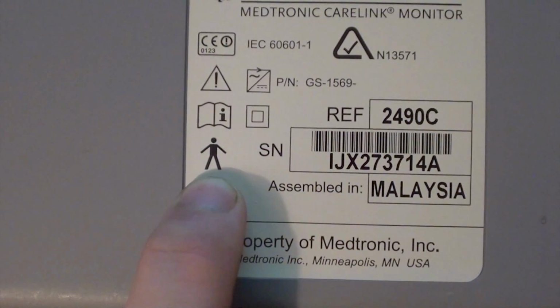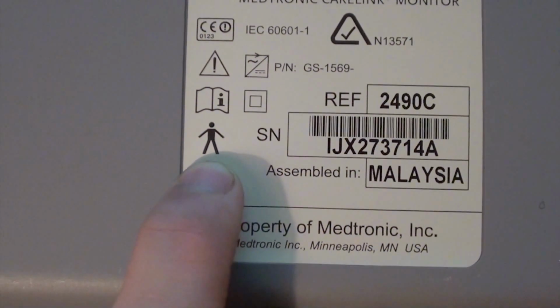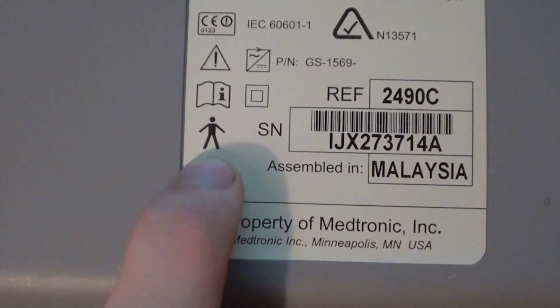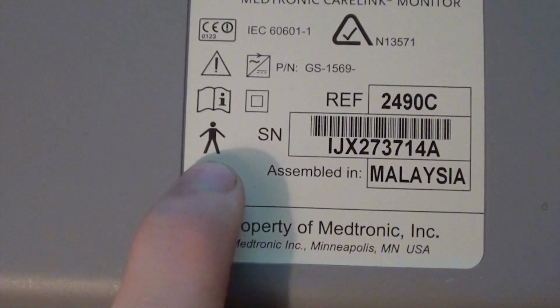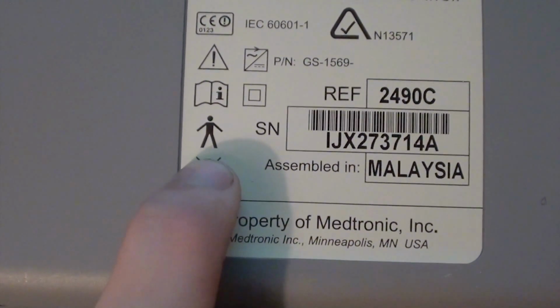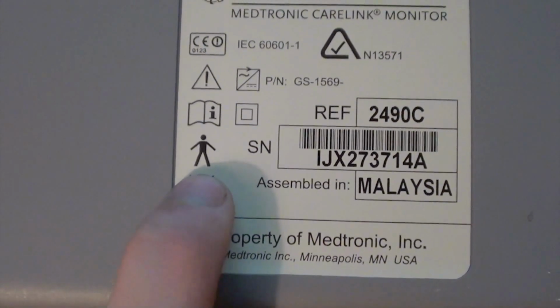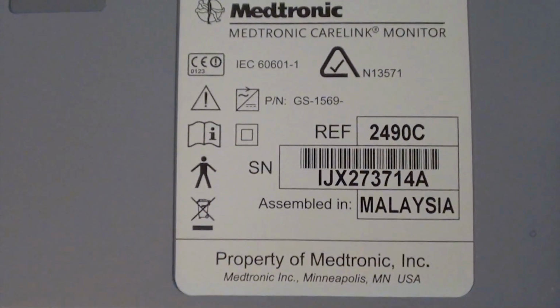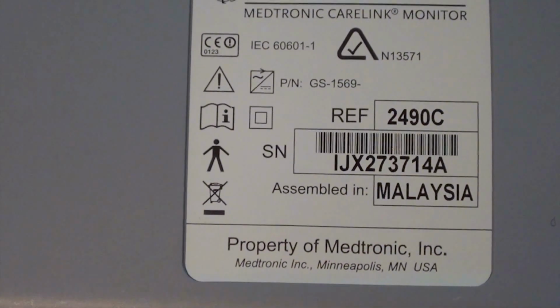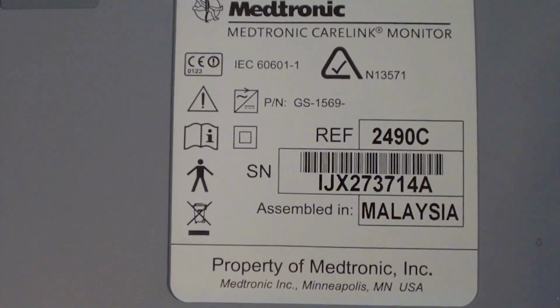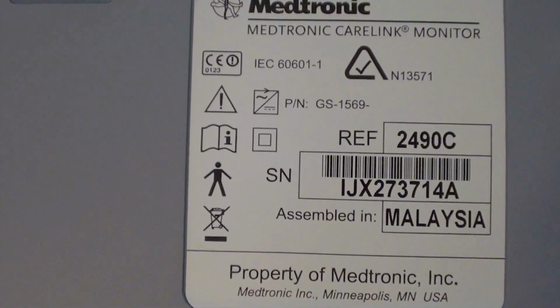This is sort of a mid-range classification. There is higher than this, which is CF. It's the most stringent classification. This would be things like pacemakers and defibrillators and things like this, but because this only picks up a signal from the pacemaker, it doesn't actually require as stringent testing as a CF classification device.